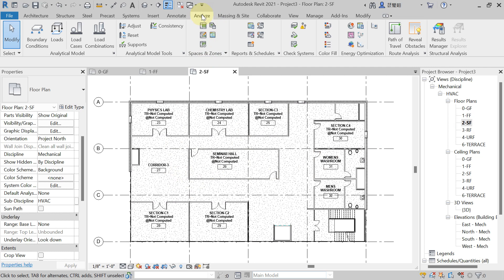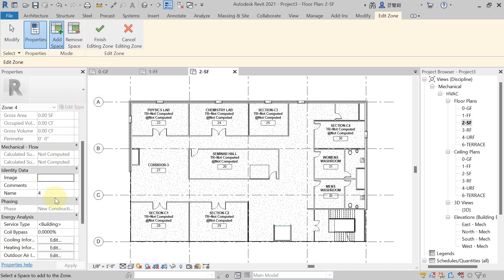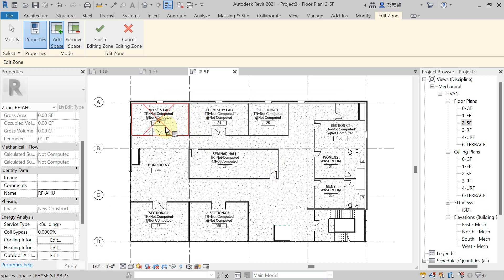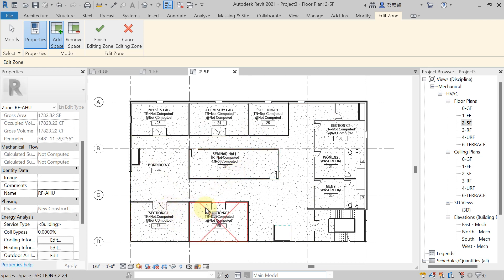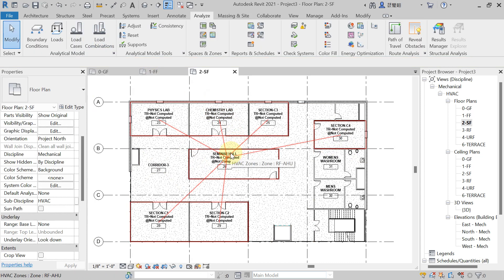Now come to the second floor. Here also we need to create the HVAC zone. Go to Analyze tab, Spaces and Zone panel, hit Zone. In the Properties palette, write the same name 'RF-AHU'. Hit Apply — you will get the duplicate name warning again, hit OK. Then select the space lines: Chemistry Lab, Section C3, Seminar Hall, Section C1, Section C2, and Section C4. Hit Finish Edit Mode. The cursor now shows all these rooms are being supplied conditioned air with the help of the AHU. This is how you create the HVAC zone.